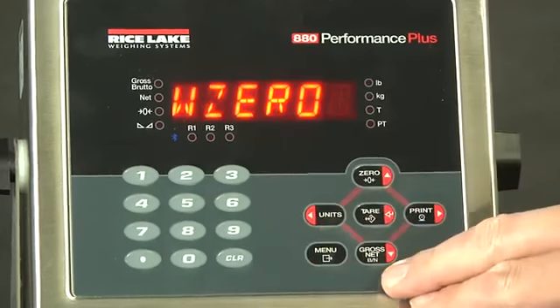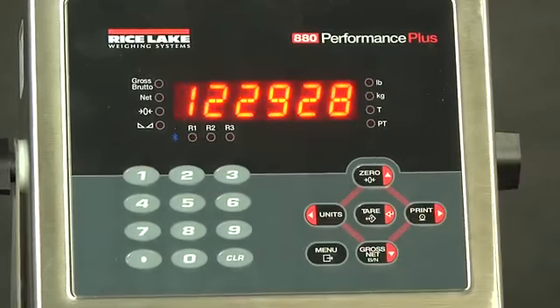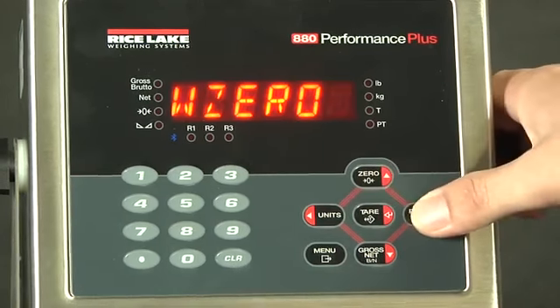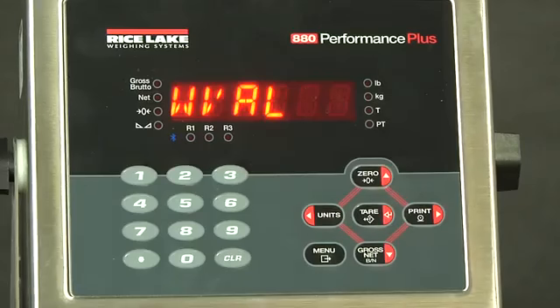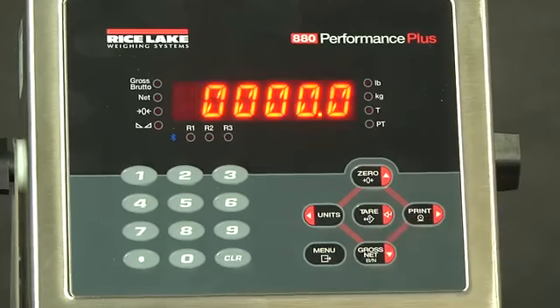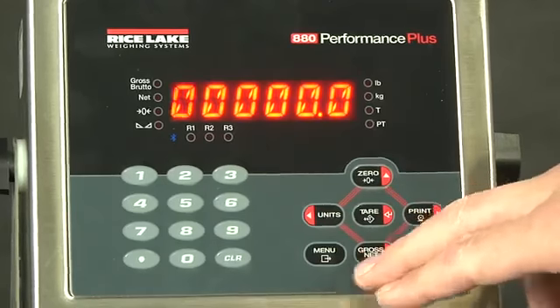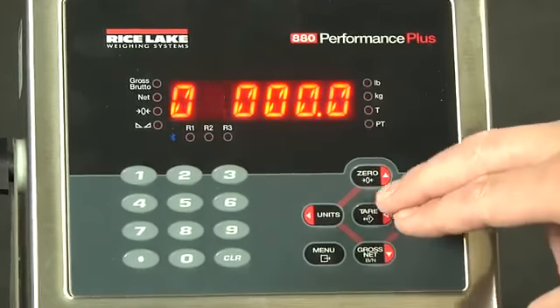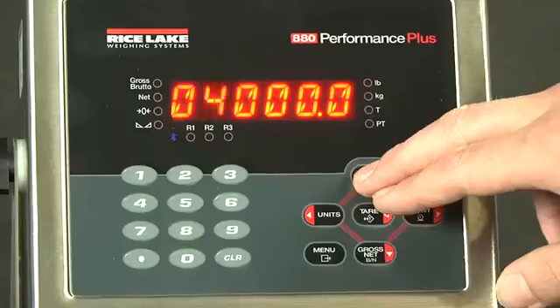If we go back, we can actually see that our number has changed. This indicates that the 0 point is now at 122,928 counts. So we will go up. WVal, this is where you set the weight that you're going to be putting on the scale. Since I am calibrating with the full 5,000 pounds, I will drop down. This is 10,000. Currently, you put down, right, and then we will go up to 5.